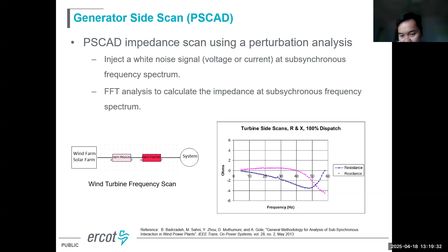So this is an example of the typical DFIG machine R and X across the sub-synchronous frequency spectrum. You may want to focus on this blue curve, which is the resistance. As you can see, for the DFIG machine at the sub-synchronous frequency spectrum, it is most negative. So that's kind of the reason SSCI relates to the defect machines.